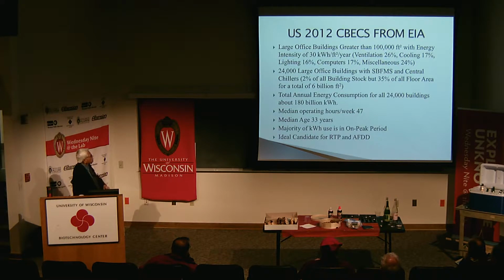And there are 24,000 buildings like this, and the total annual energy consumption of all these buildings is 180 billion kilowatt hours. And the median operating hours is 47 hours per week, which is important. That shows there are occupied periods and unoccupied periods, which is very important for us when I talk about fault detection and diagnosis, or when I talk about demand response. The median age of all these buildings is 33 years. Now these are, as I said, ideal candidates for real-time pricing, RTP, and automatic fault detection and diagnosis, AFDD.